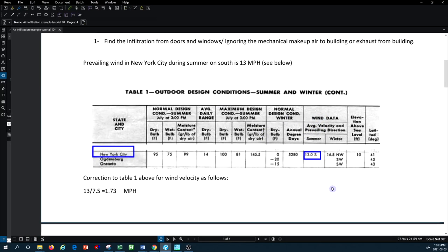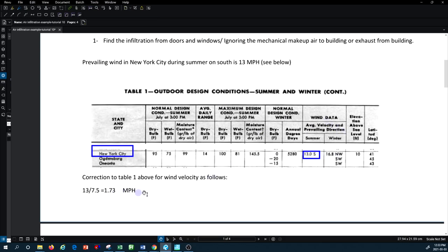First we have to correct the velocity for our case. Because the tables for air intake through windows and doors are based on a wind velocity of 7.5 mph, we have to correct our value. We divide 13 — our wind velocity for New York City in summertime — by 7.5. Note that the winter wind is higher than the summer wind. This gives us a corrected wind velocity factor of 1.73 for the tables we are going to use.